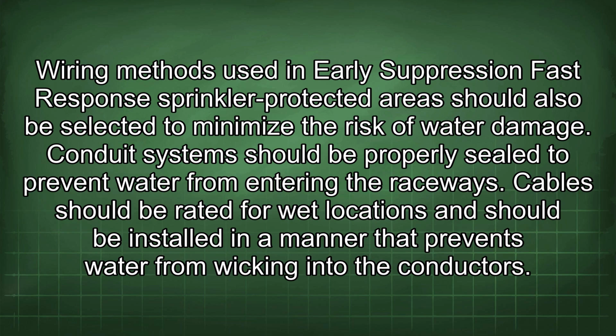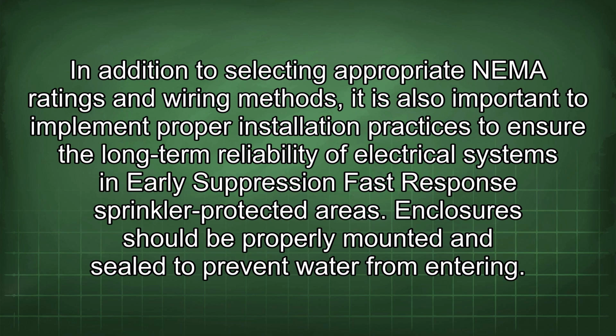Conduit systems should be properly sealed to prevent water from entering the raceways. Cables should be rated for wet locations and should be installed in a manner that prevents water from wicking into the conductors. In addition to selecting appropriate NEMA ratings and wiring methods, it is also important to implement proper installation practices to ensure the long-term reliability of electrical systems in early suppression fast response sprinkler protected areas.